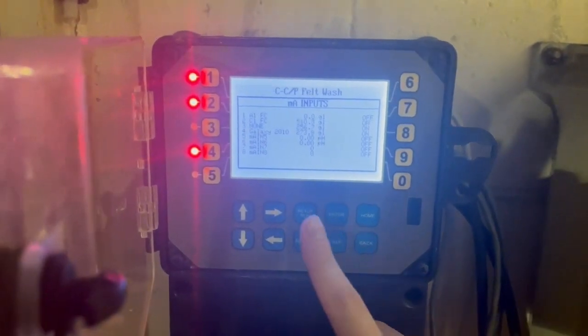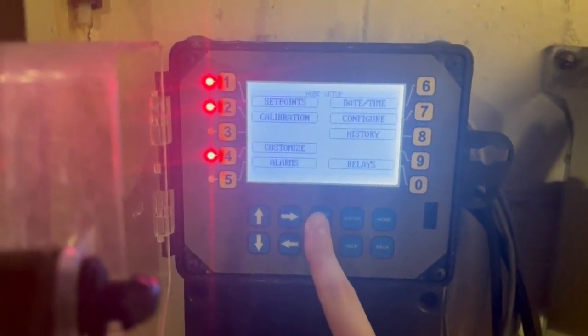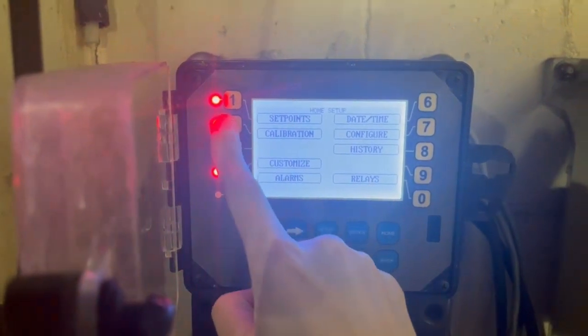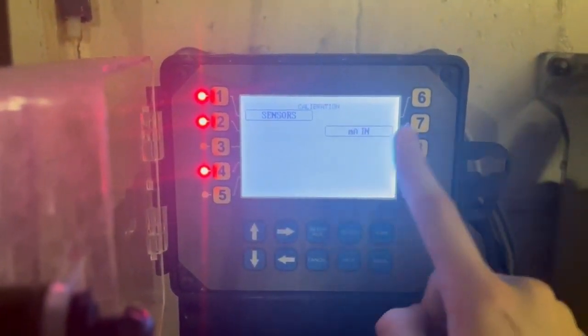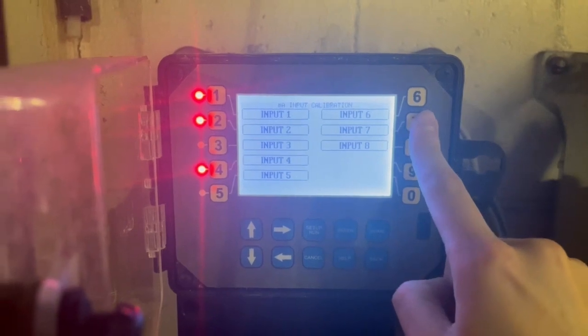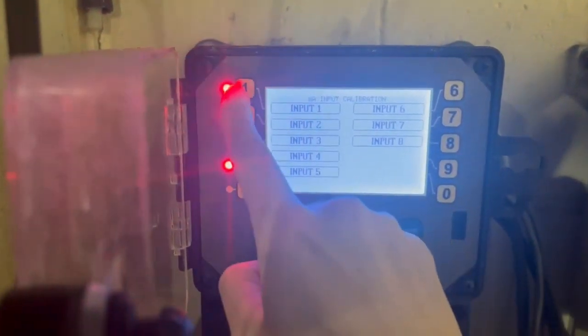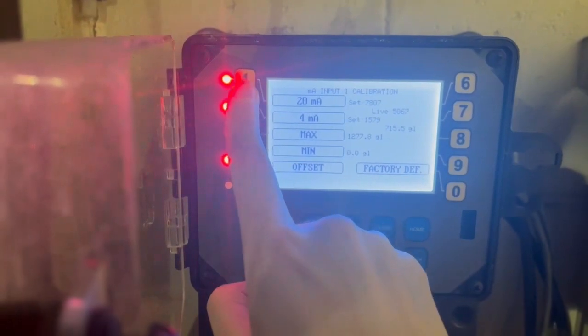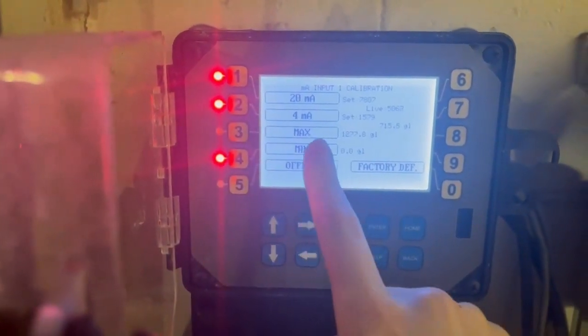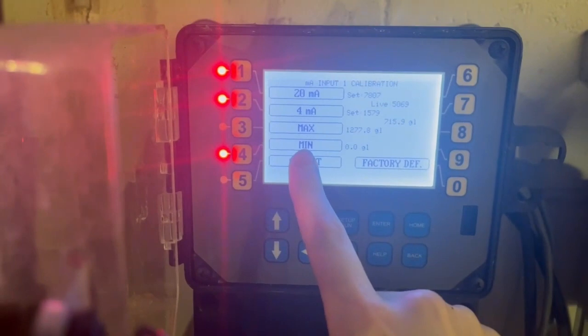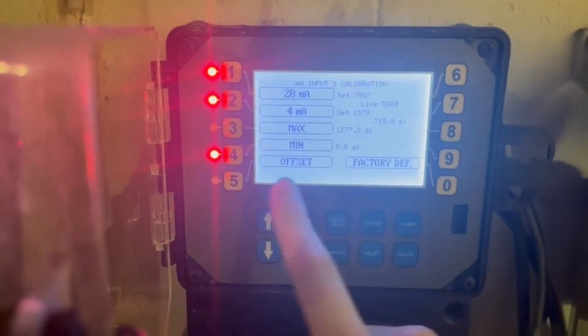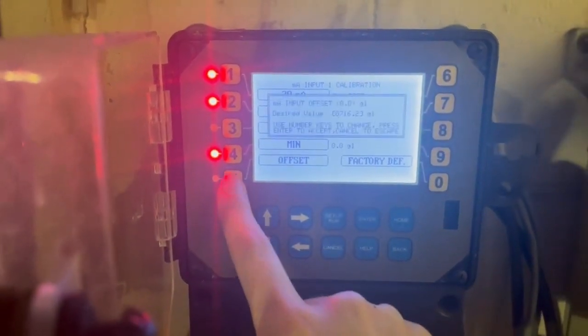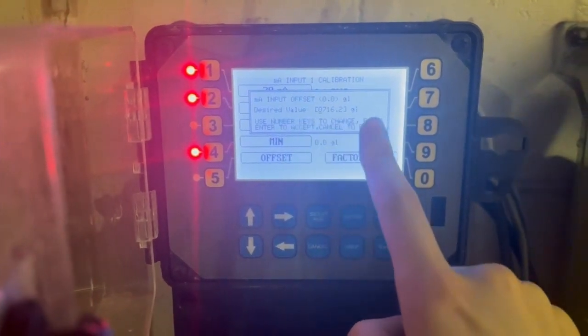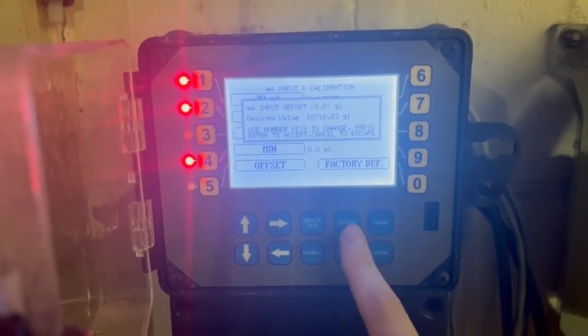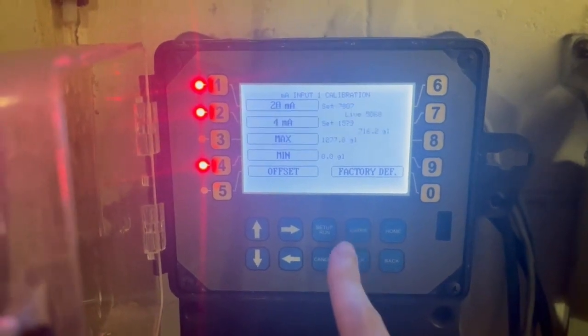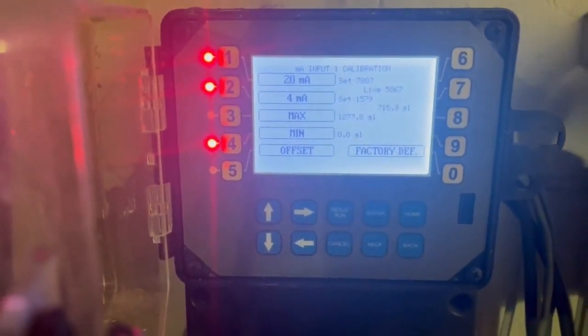Going back to the monitor, select Setup Run, and then select Calibration. Then select Milliamp Input, and then select Input 1. Follow the instructions in the SOP document as to what value to put in for the max value. For the minimum value, put in 0. And then for offset, put in the current amount that is currently in the tank, and then select Enter. Turn the monitor on and off, and it should display the current amount in the tank.